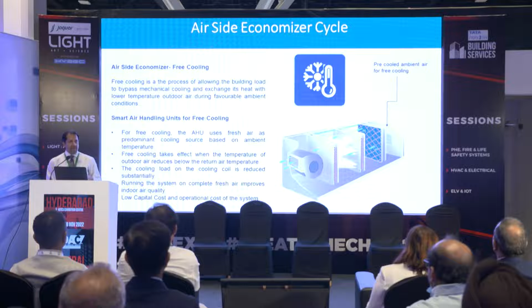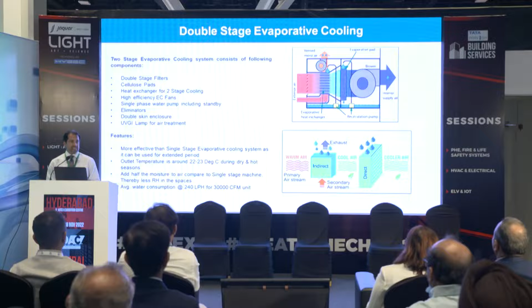Evaporative cooling is making a comeback. People are asking, why don't we go to evaporative cooling? Double stage evaporative cooling can give long hours of cooling without requiring any compressor-based systems, and it's far cheaper.